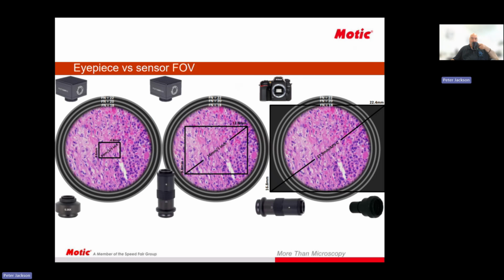It's worth noting that the FOV, or so-called field of view, that you see will depend upon the eyepiece size that you've got in your microscope. So here's an example of some different eyepiece sizes in terms of millimeters. Obviously, the bigger the size of the eyepiece, the more you'll see of the slide. And the bigger the sensor, the more you'll also see of the slide when you look at the digital image. So for a small A5 camera, which has a 1/3 inch sensor, you're not seeing all the slide, you're just seeing a part of the slide.